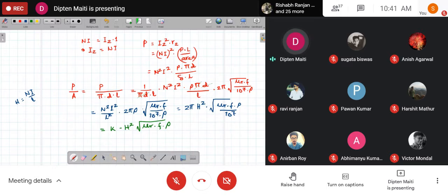Of course, depending upon the time, as the structure melts, that would become thicker and thicker. So we need to take into account the frequency, how long the operation would be continued, and what temperature needs to be generated. That sort of thing needs to be taken into account while going for selection of the frequency for the induction furnace.